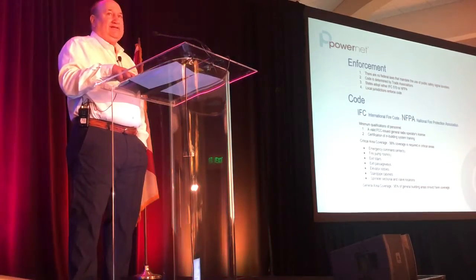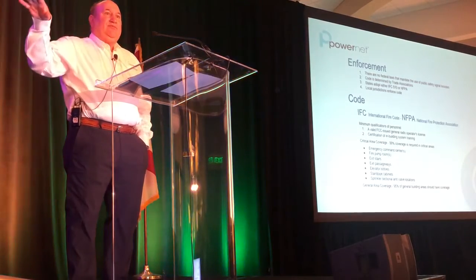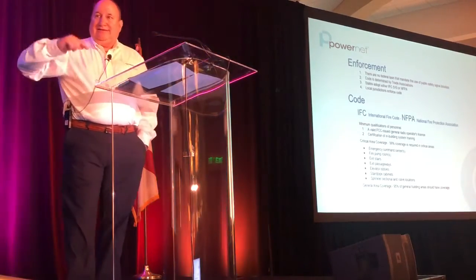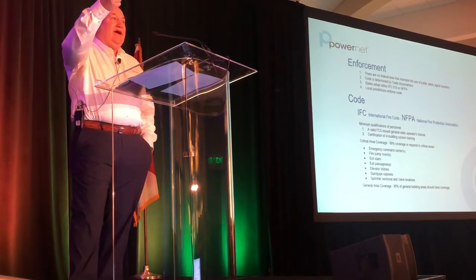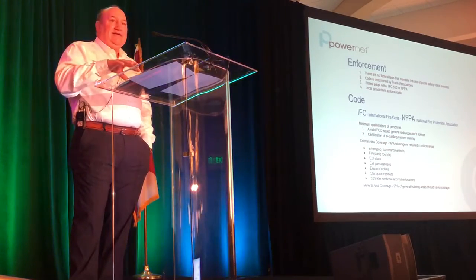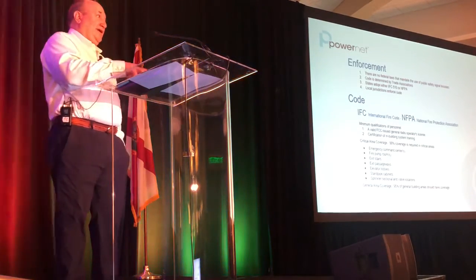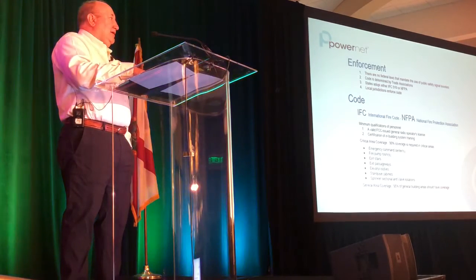One of the things that's driving this, in 2015, Broward County had an issue where several of these systems were put in and caused interference on the county system. By the way, if you put the system in, and the uplink side of that, which handles amplifying their talking back to their tower, talking back to their dispatch center, is not handled correctly, it can take down the system for the entire county. So you've got to make sure that you're dealing with a reputable firm that understands that and is working hand in hand with the fire chief or the radio operator for that county.